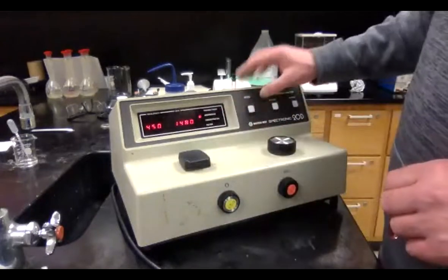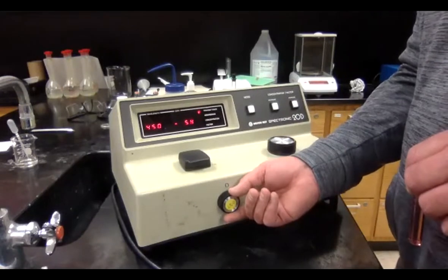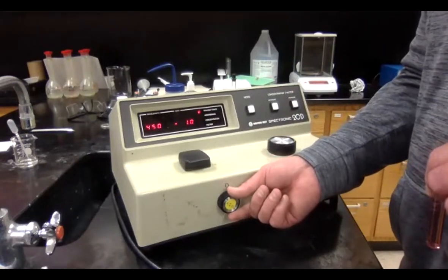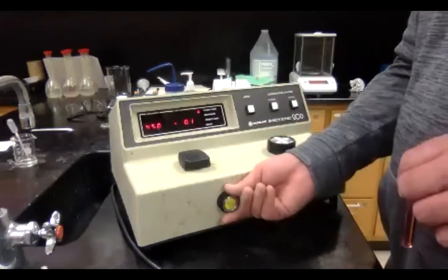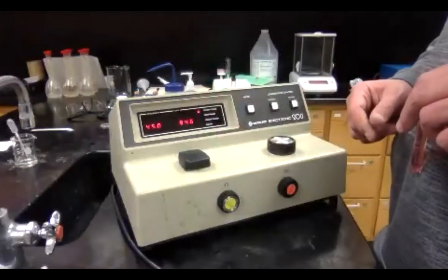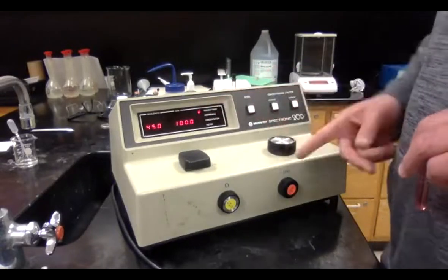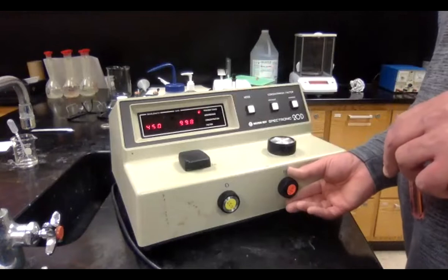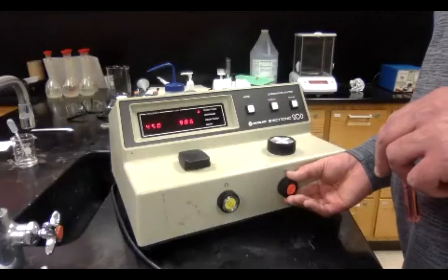Oh, I'm sorry, I'm on absorbance. I need to be on transmittance. At transmittance, we need to be at 0. We need to do every single part of this again. So we have that at 0. And sometimes, if I hadn't messed with it, we might have been okay. Now the blank. See, we didn't touch the 100 one. You're not paying attention. So we are actually very close to good on the 100 one. Come on now.